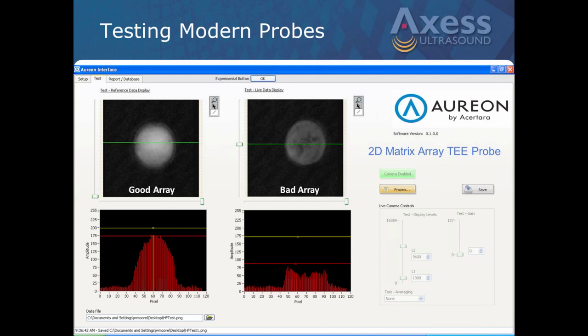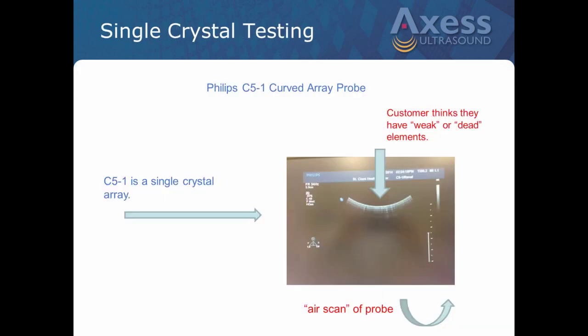But this is a great device in the fact that with the Aureon you can test single crystal arrays, composite arrays. It doesn't matter. It tests them all because it's looking at the acoustic power to the array. Whereas the FirstCall is somewhat limited as to how many elements it can test, the Aureon doesn't care. It can test regardless of the number of elements. Really unique tool out on the market right now.